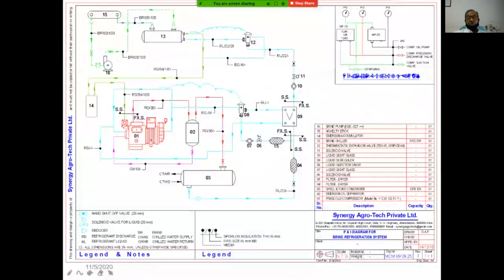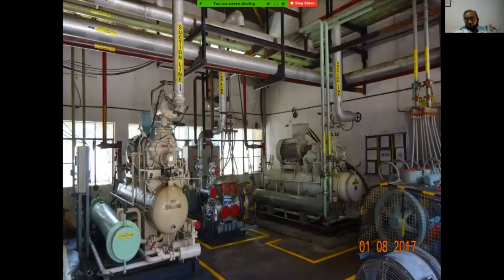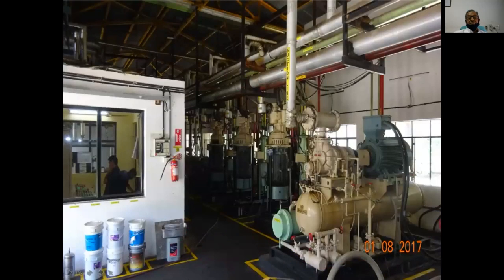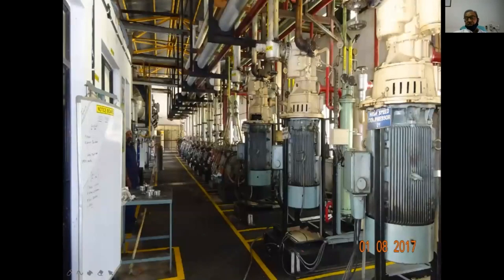The refrigeration system for that brine cooling is again a two-stage compression system, but here instead of an evaporator it is a chiller, a saline chiller, a shell and tube chiller. How it looks, a plant of the ice cream industry. It is not this screw compressor. You can see the plant. It is a very big size plant. It's a complete plant of that. This is a complete plant of the ice cream industry, producing 1 lakh liter per day ice cream. This plant we installed in Nagpur.